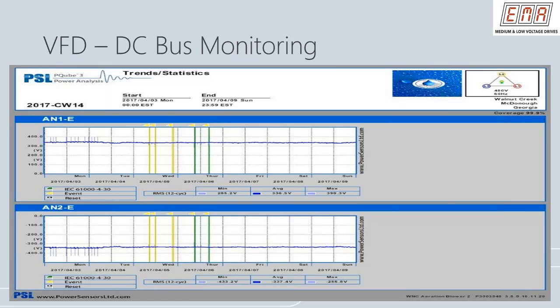Which gives you about 650 volts nominal. So now, when we have a failure on the snubber network, we are seeing 850 volts on those DC bus capacitors. What that does is puncture holes in the insulation of the capacitor and cause significant leakage current, and as a result, capacitor failure.